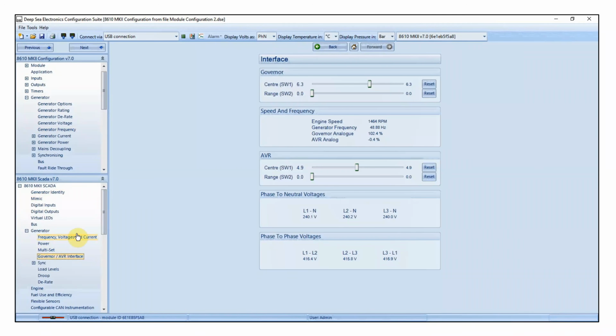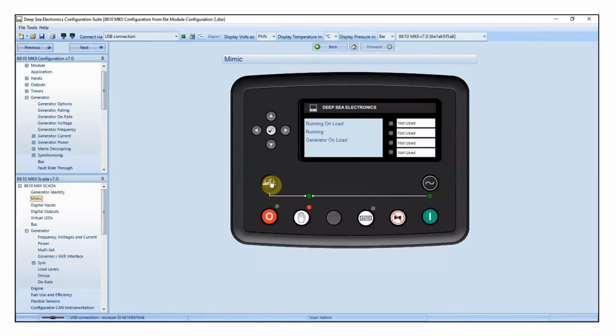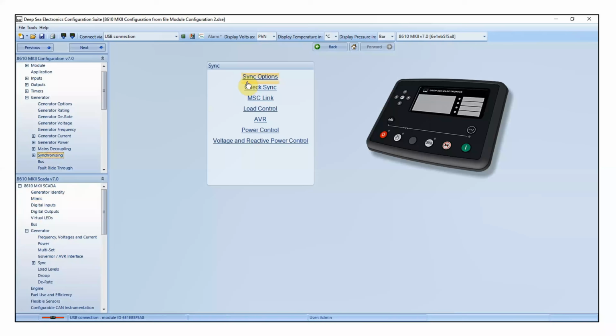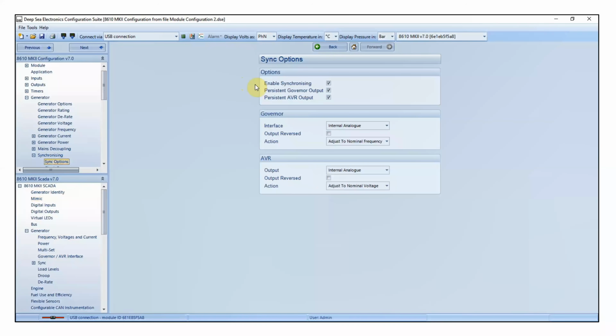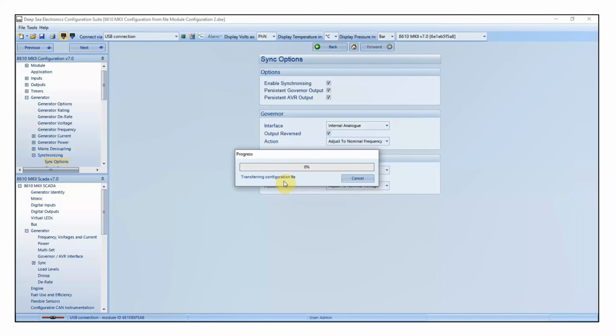However, in this case, you can see the frequency for some reason has decreased. This has happened because as we increase switch 1, the frequency decreased. Now, what a lot of people would do here is go and change the wires around on the back of the DSE module, but that's not the correct thing to do. What you need to do is go to the generator synchronizing sync options and tick the option output reversed, as I've shown here. This is the only thing we've changed, the tick box for output reversed. We're going to start the generator, and if we close the breaker this time, you'll see that the frequency, instead of going down, will now go up. This is what you should always do in this instance. Never swap the wires around on the back of the DSE module.